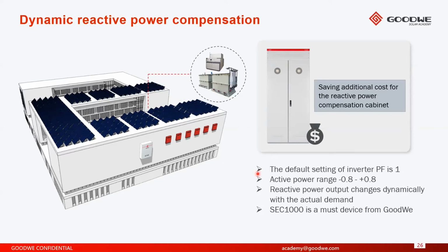Our inverters have the ability to support or supply reactive power into the grid so that the power factor improves and gets much closer to unity, or a power factor of 1. This dynamic reactive power control can work day and night, 24 hours throughout the day. So this reduces the penalty costs of having a low power factor for the industrial customer.